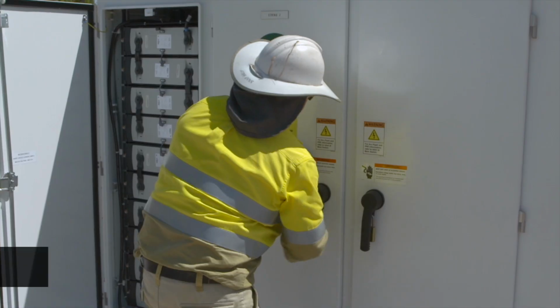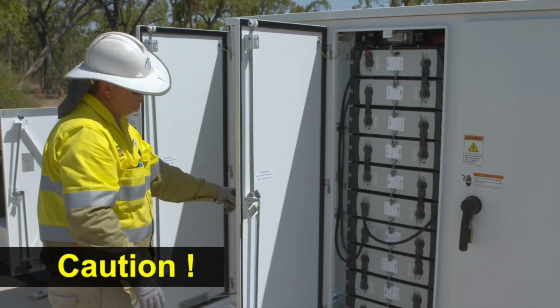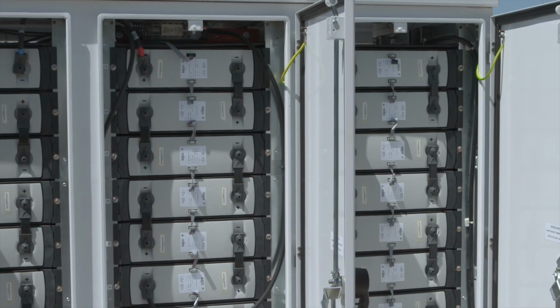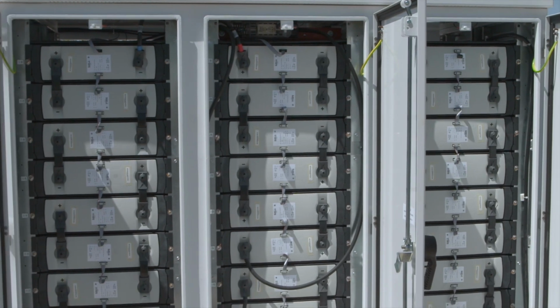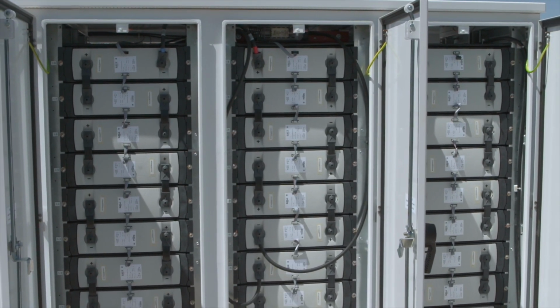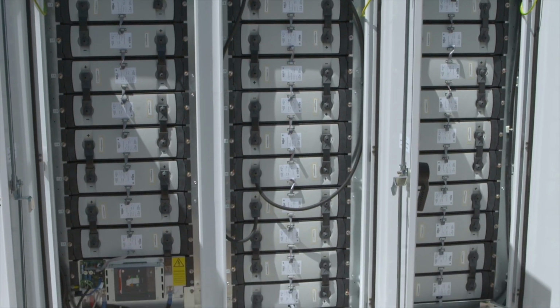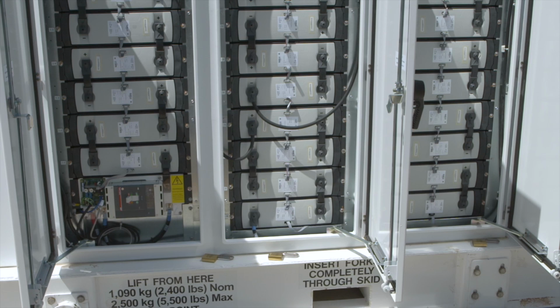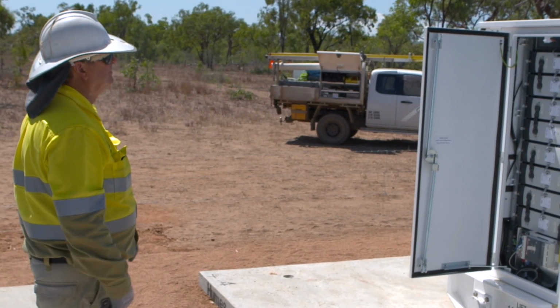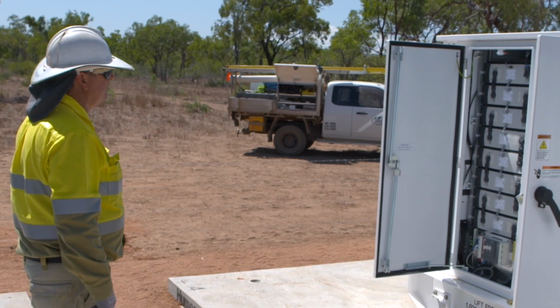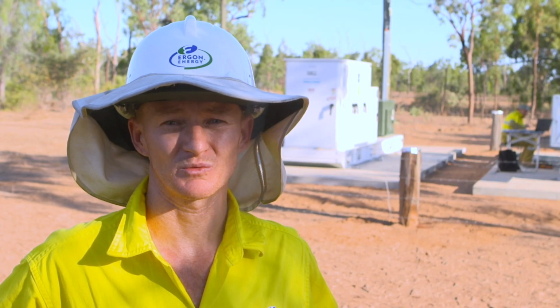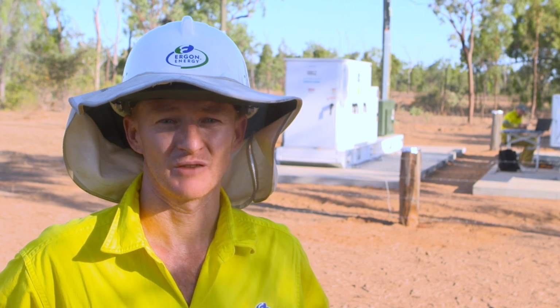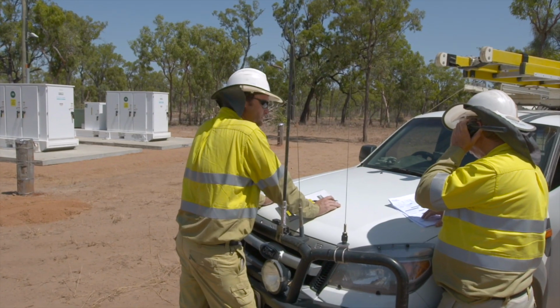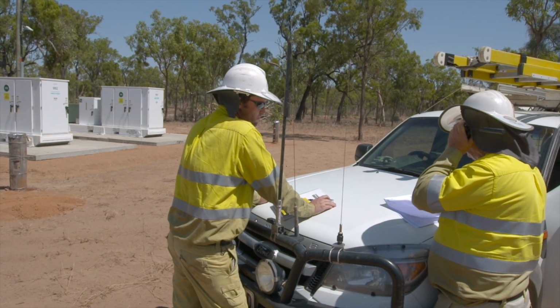When opening the battery bank cabinet, open the doors and stand back for 1 minute to allow any potential hazardous fumes to dissipate. Visually inspect the batteries and equipment for any damage, burning, smoke or fire aerosol residue. You must do this at all times even if there are no faults. In the unlikely event the fire canister operates while working with the doors open, evacuate the area. Go to the upwind side of the container and contact the GUSS engineer.